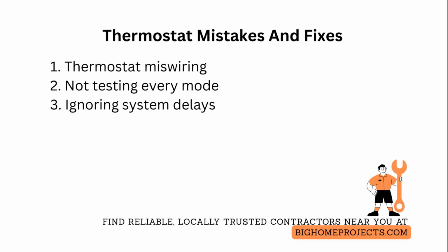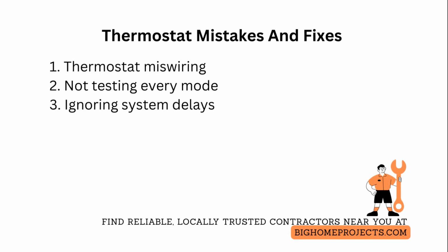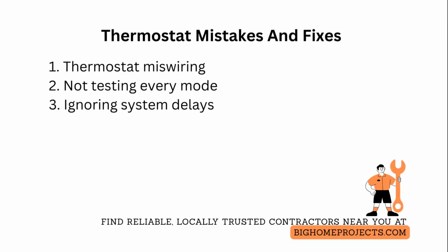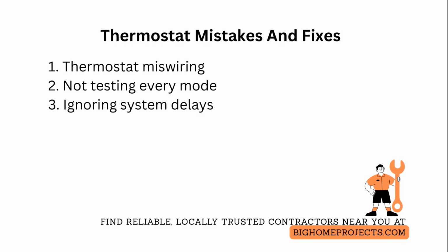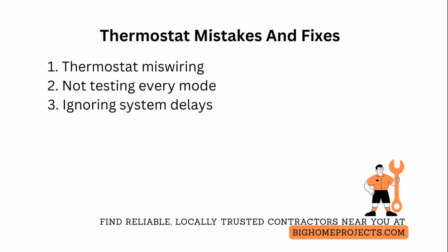One of the other common issues is ignoring system delays and protective timeouts that make functions seem non-responsive. Fix by waiting the full 2 to 5 minute compressor lockout or cycle delay, checking for error codes, and confirming each mode shuts off properly to avoid short cycling and tripping safety switches.